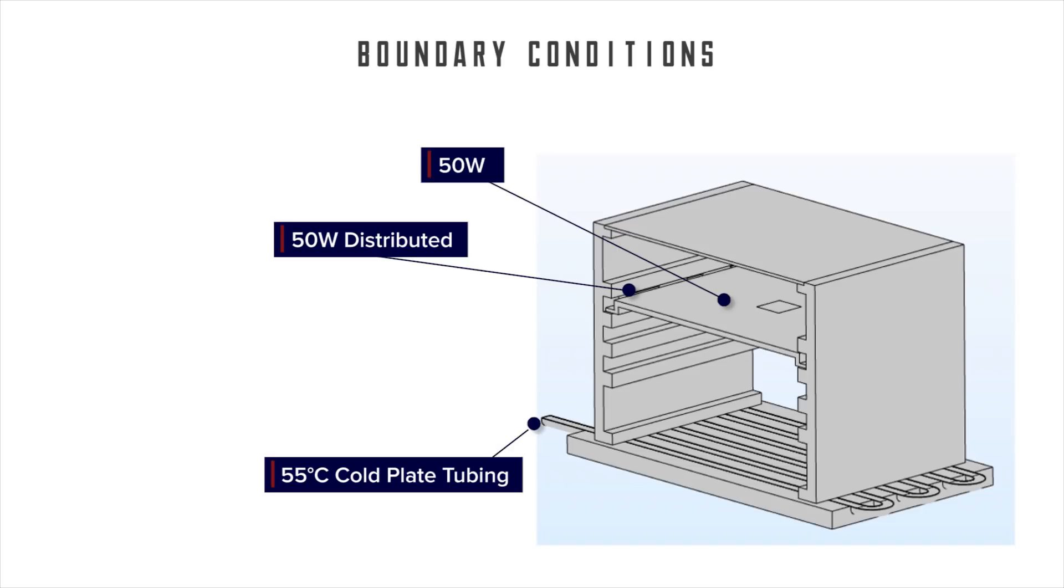To successfully reject the waste heat to the liquid-cooled base, the heat must conduct from the components to the conduction card frame edge, through the mechanical retainer or wedge lock, and down the card guides to the liquid base.